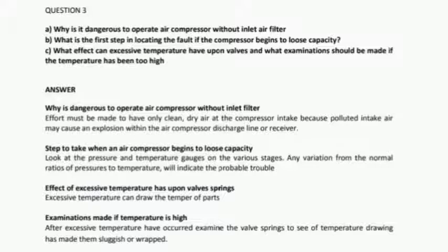Effort must be made to have only clean, dry air at the compressor intake because polluted inlet air may cause an explosion within the air compressor discharge line or receiver. When air compressors are operated without inlet air filters, foreign matter such as abrasives in the air is allowed to enter the compressor. It combines with oil to form an abrasive-like paste, which will increase wear on piston rings and liners and may choke the valves.